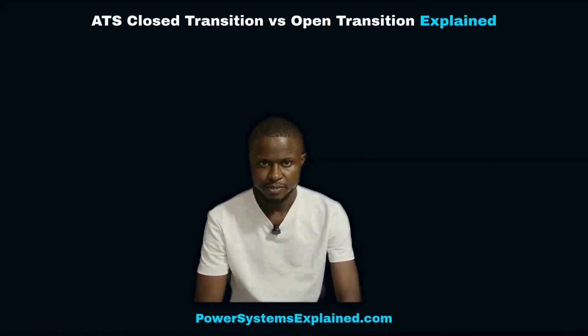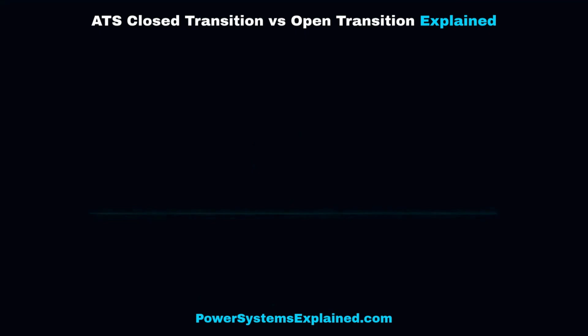Here is the big picture. An ATS doesn't fail quietly. It fails invisibly. The switch operates exactly as programmed every time. The problem was never the switch. It was whether the switch was configured for what's actually connected to it. Check that before you trust the system, not after something trips.